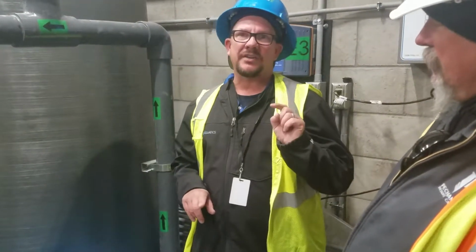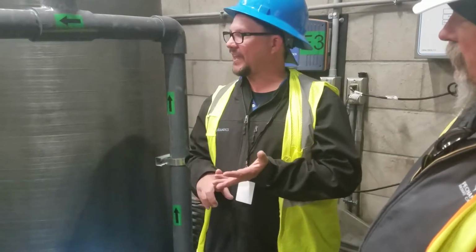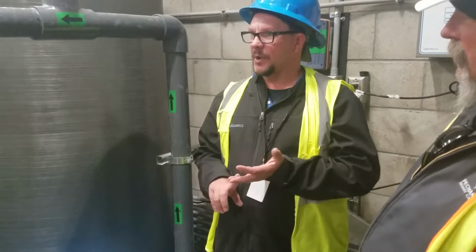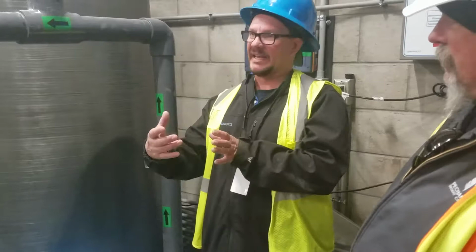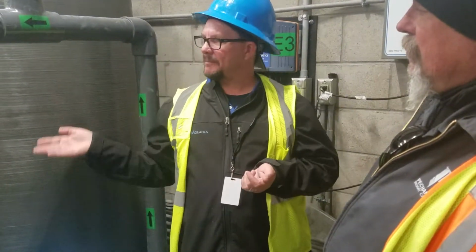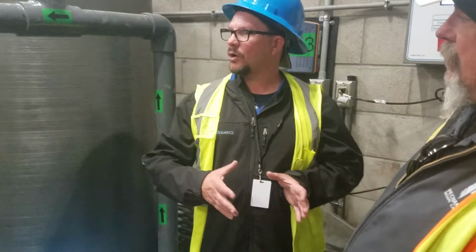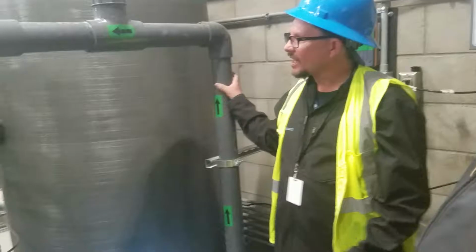As you delve into it a little bit more, it'll actually let you know how long the pumps and things turned on for. So if you know you have a number 5 squeeze tube on a Stenner pump and it's set at the max and it pumps 85 gallons per day, mathematically you can figure out how much chlorine did I use in a certain amount of time. Well, that's a deeper conversation we can have with your guys' staff.